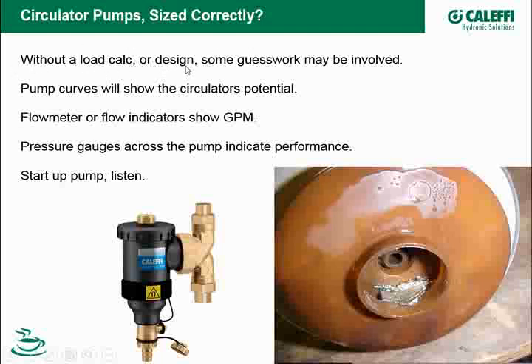Again, without a load calc and knowing the original design on it, there may be some guesswork involved in pump sizing. You go to a job, there's no documentation. All the pipes are, of course, closed up in the wall. You can't see what's going on. You don't have the heat load calculation. So that's another thing we're going to talk about in the webinar in December: how to tell what the pump that you've got in there is doing, how to build a system curve and analyze if it's the right pump, and what you can do to correct or change that.